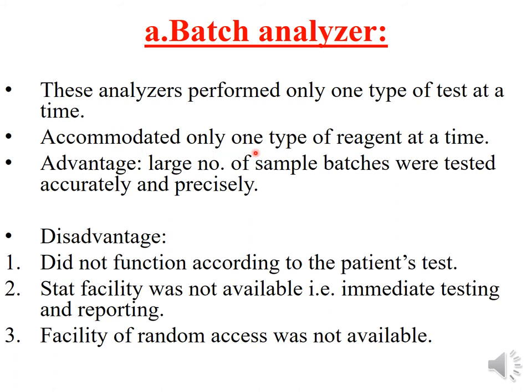Only one type of reagent can be accommodated at a time, so you cannot do glucose, urea, and creatinine all together. Advantages: a large number of samples can be analyzed in batches, and the testing is done accurately and precisely.